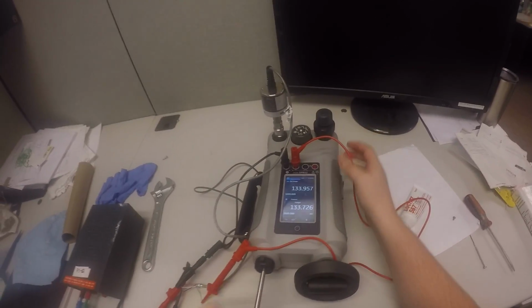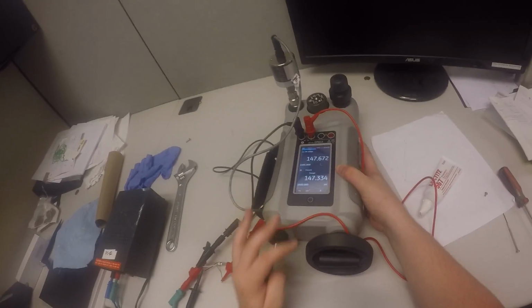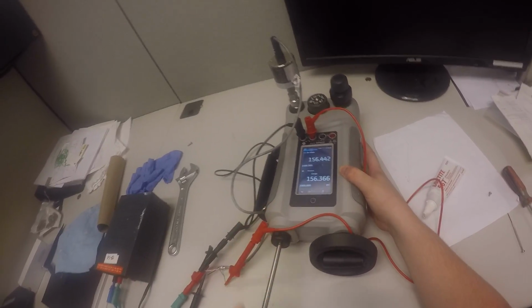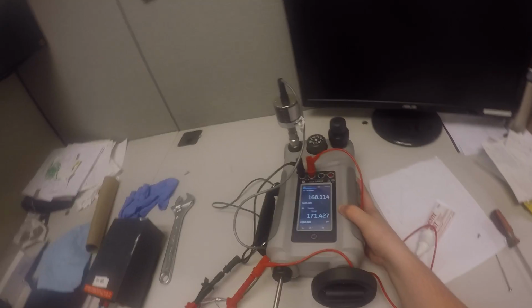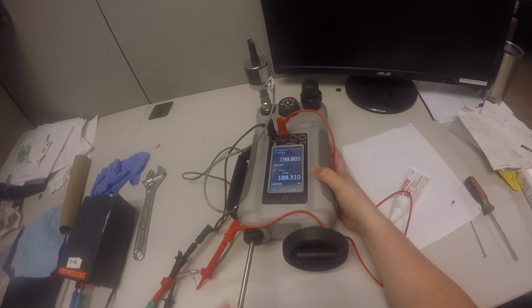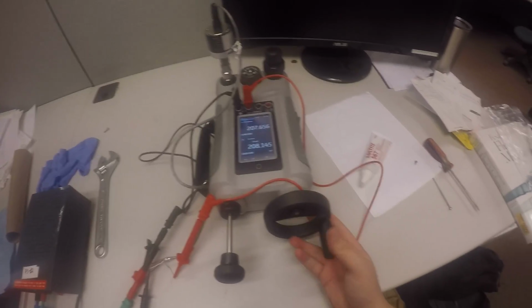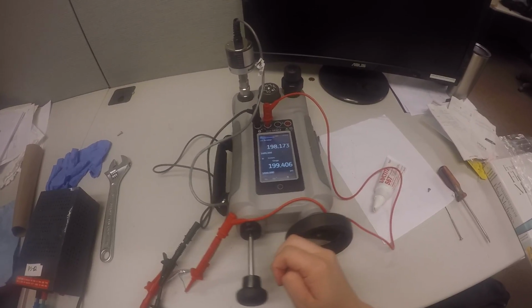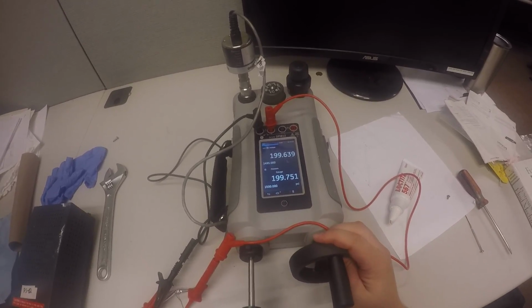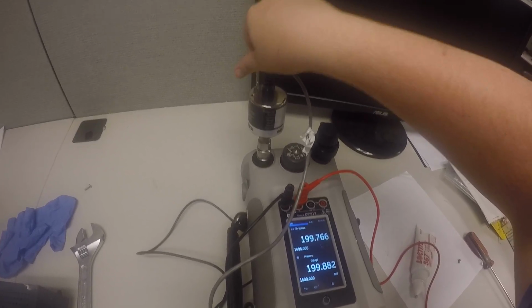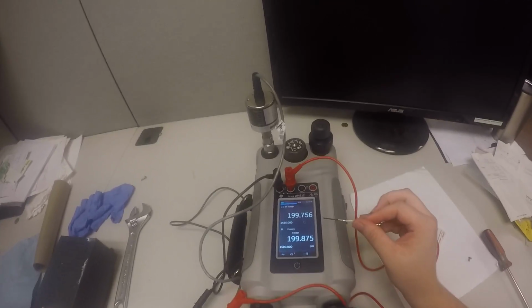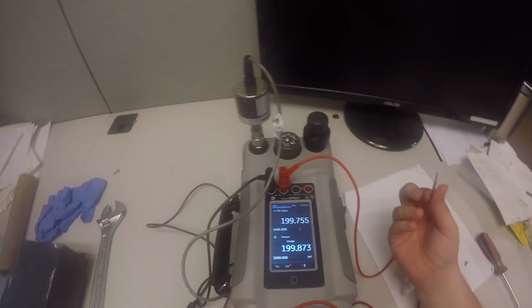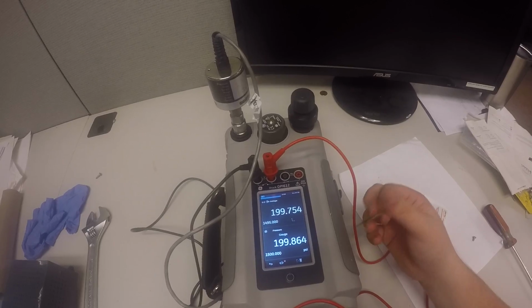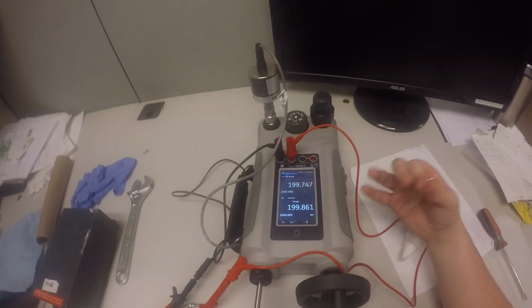And this shaft has more output for the pressurization than the wheel does. The wheel is more for accuracy, and this one's more for quickly pressurizing the Druck. Alright, now that we're up here, maybe we'll use this wheel to go down a little bit to get closer to 200. There we go. So now we're at about 200, and we're going to adjust the second hole on top of the transducer. I'm going to go down there and find the screw, and you want to get the measurement on top close to measurement on bottom, probably within 0.1 psi or a little bit less than that maybe. You just need to get it close and to where it's good enough, basically.